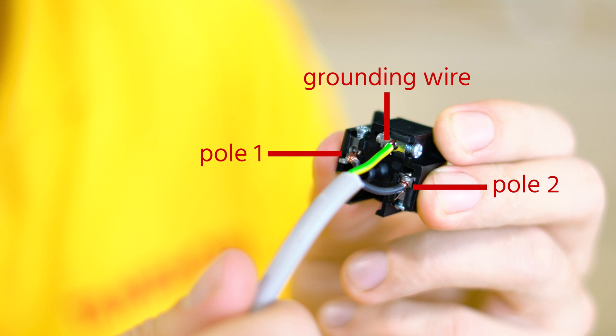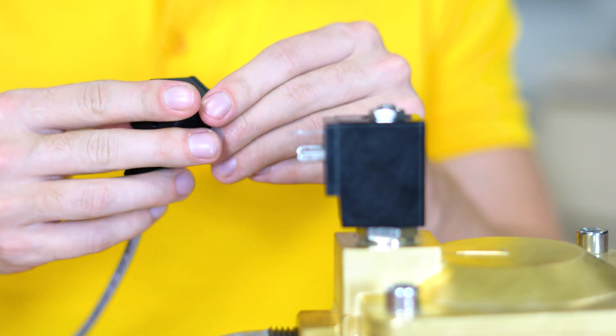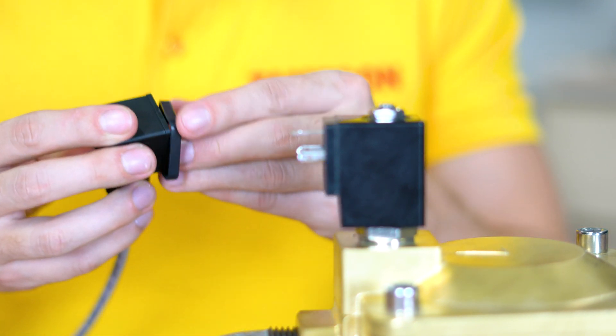Always connect to the earth or grounding wire. Never use the pipe itself for this. Ensure the connector is on properly, so that no moisture comes between the coil and the connector.